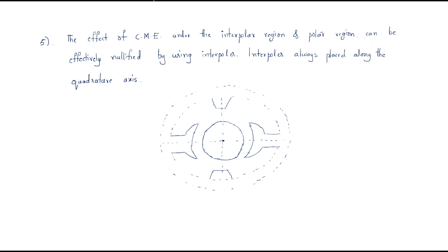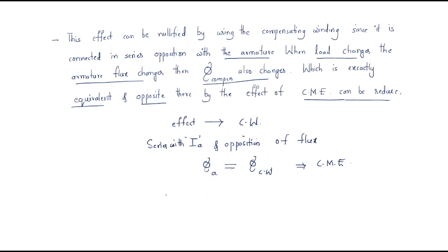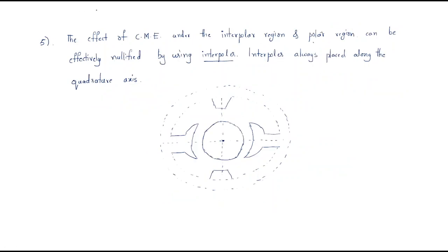The effect of cross-magnetizing effect under the interpolar region and polar region can be effectively nullified by using the interpoles. Cross-magnetizing effect is generally caused by load changes — this is the main reason. We have two regions: the interpolar region and the polar region, and both can be effectively nullified using interpoles.